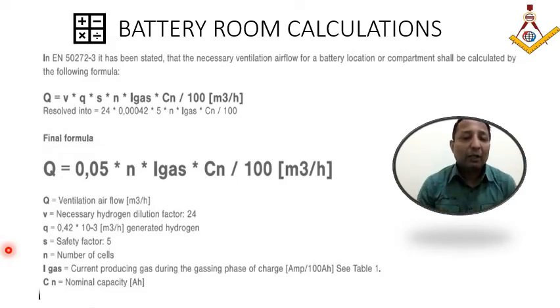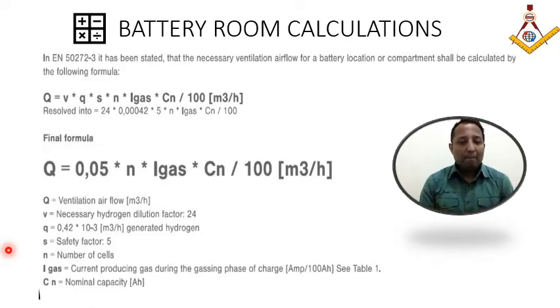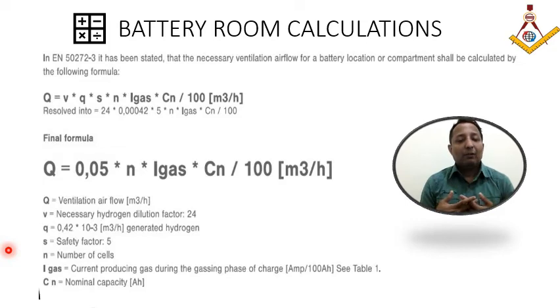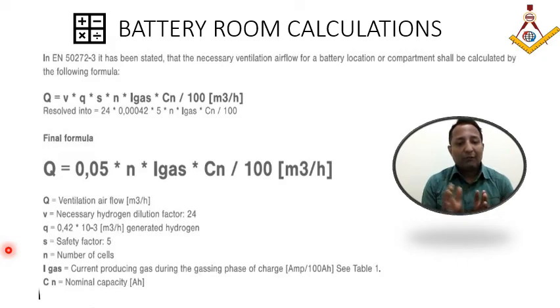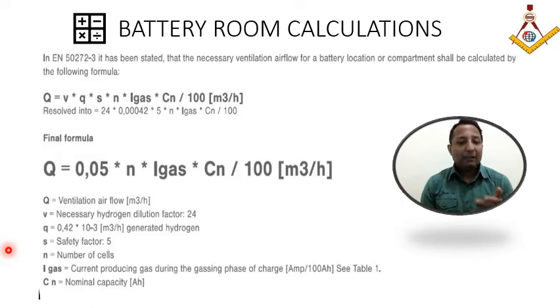If you see this formula carefully, this is the formula applied to calculate the ventilation rate to take out the hazardous gas outside. Additionally, 12 air changes is the standard industrial practice — whichever is higher between the formula result and 12 air changes is taken into consideration while designing the battery room ventilation system.